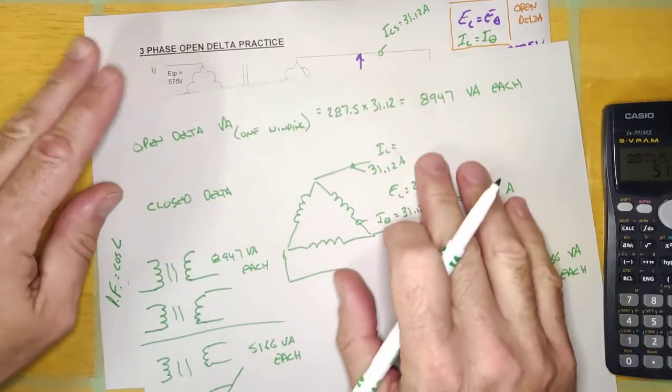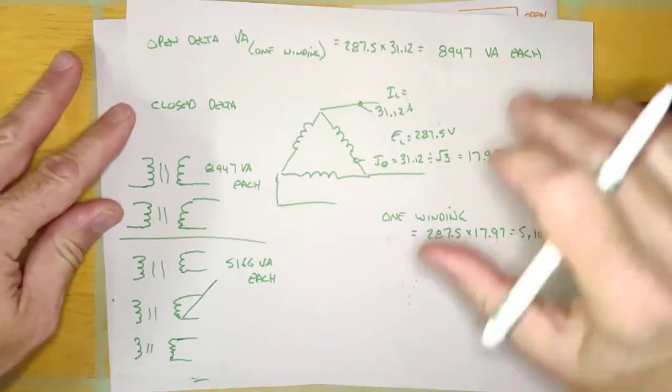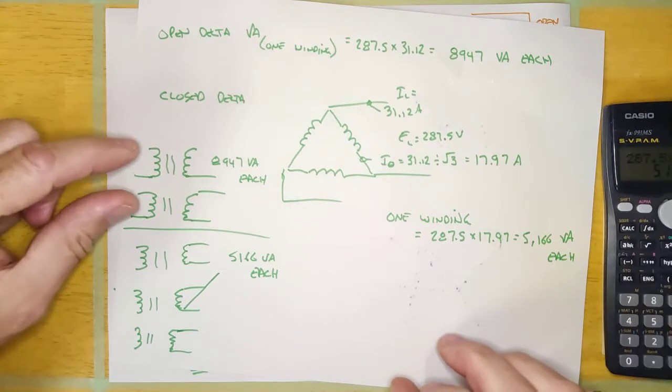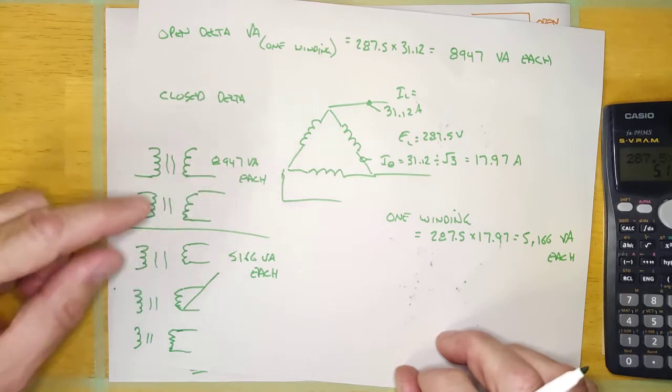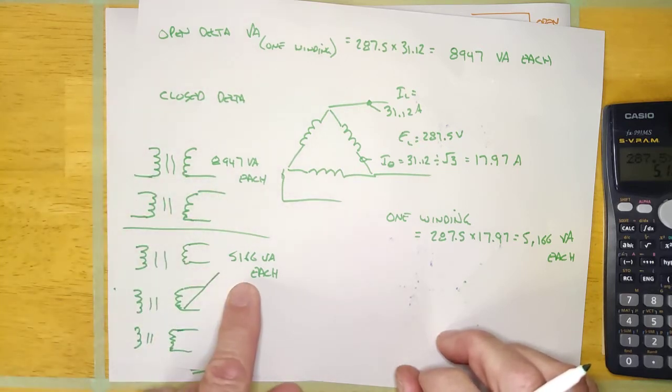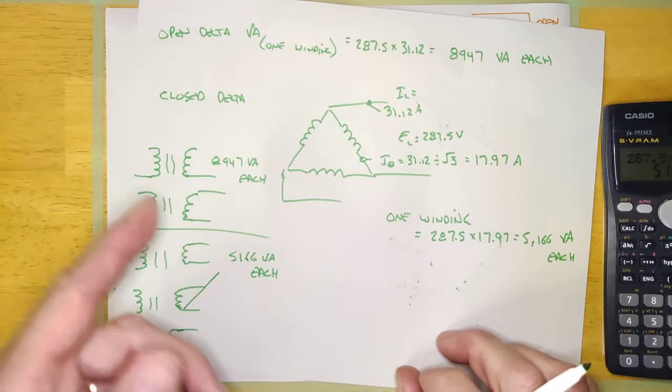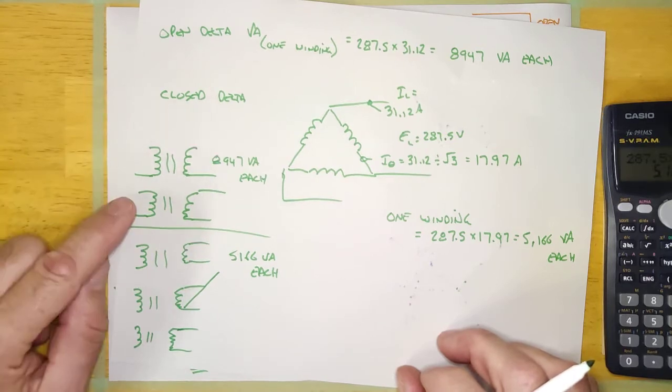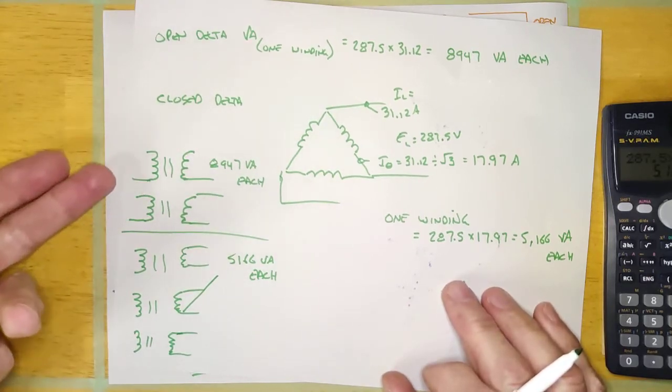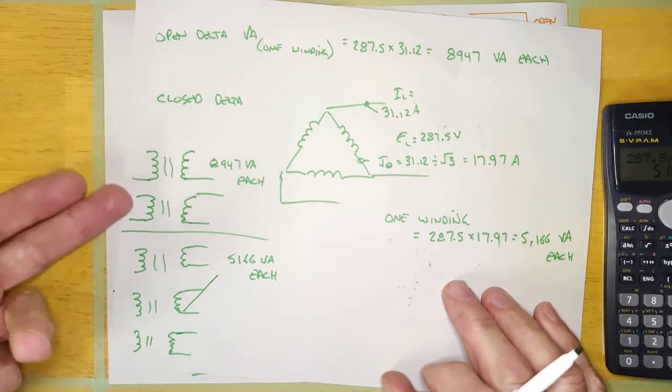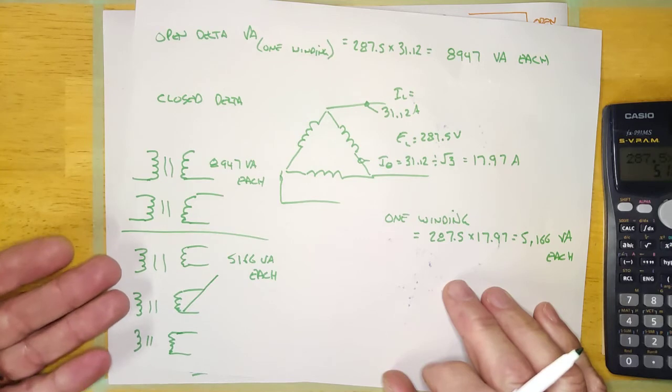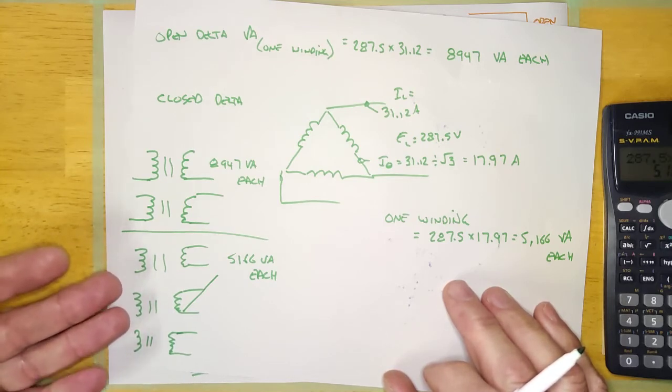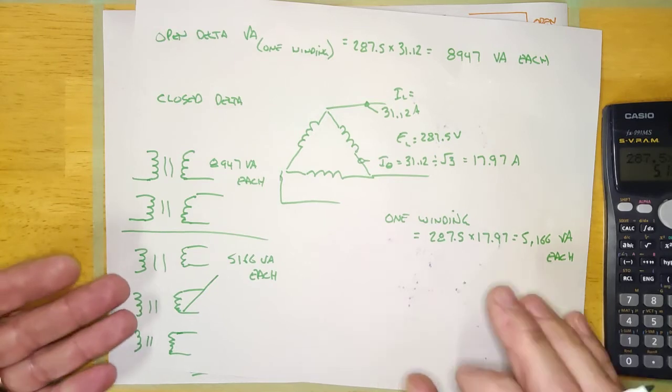It doesn't make any difference and it doesn't know. So the only difference between open delta and closed delta is open delta is two transformers that are big and closed delta is three transformers that are small. And so you're literally going to call the supplier and say, hey, quote me two 9 kVA transformers, single phase transformers, so I can connect my open delta transformer, and quote me three 5,166 VA transformers, three of them, so I can feed my load three phase load.